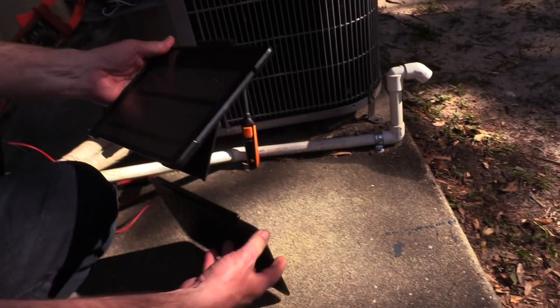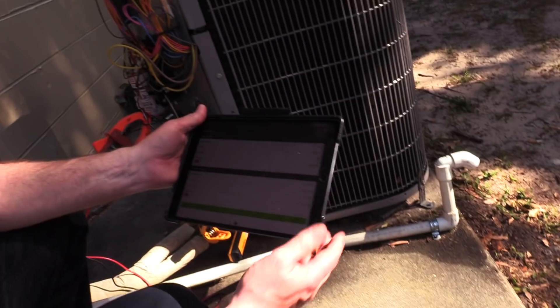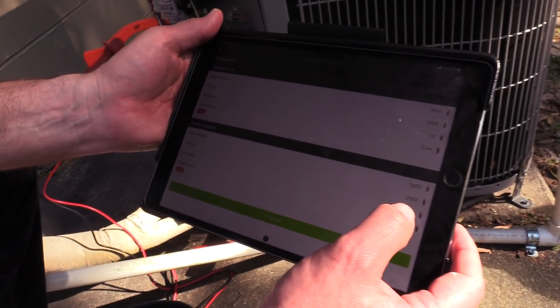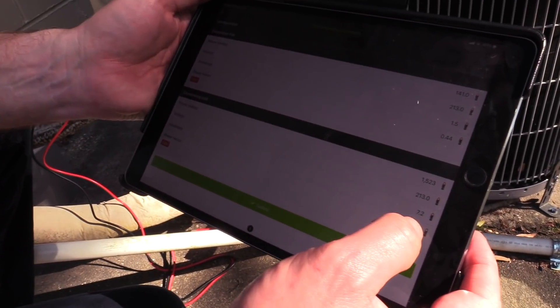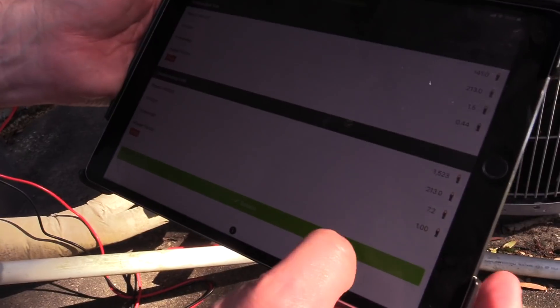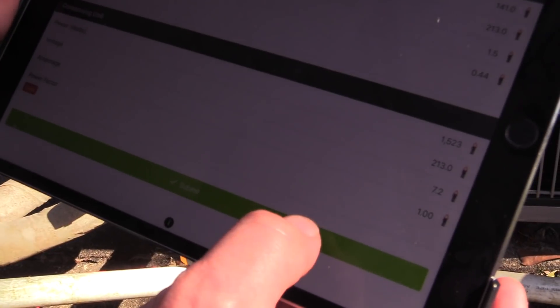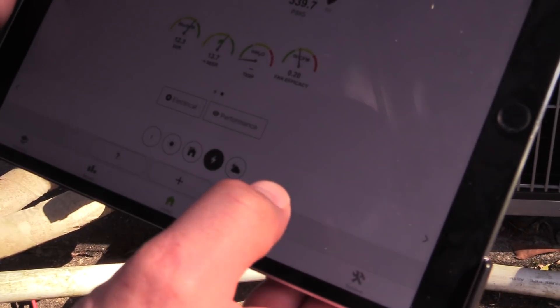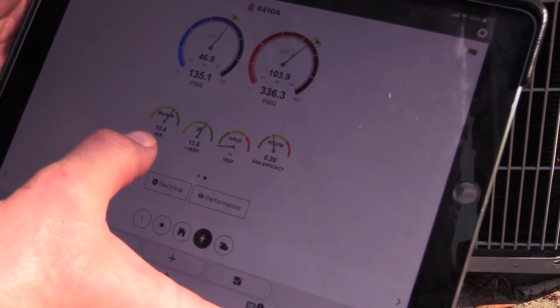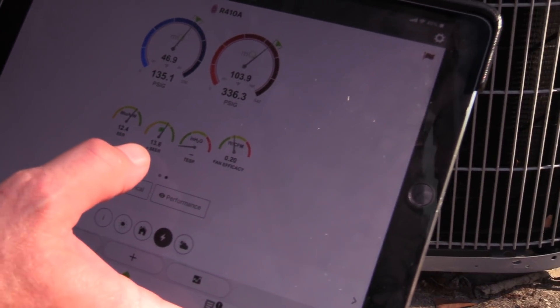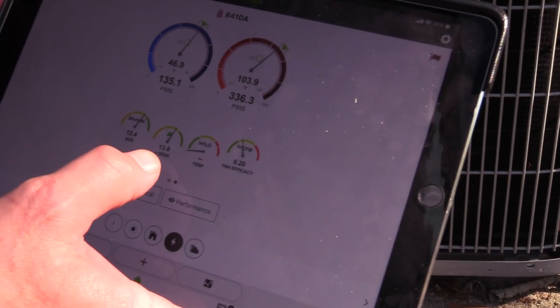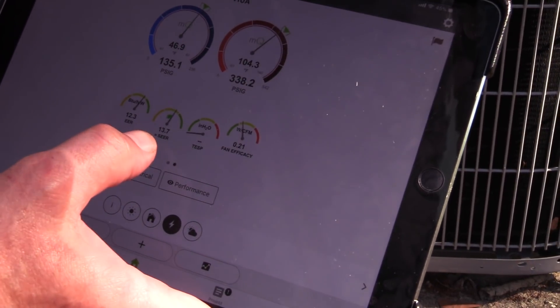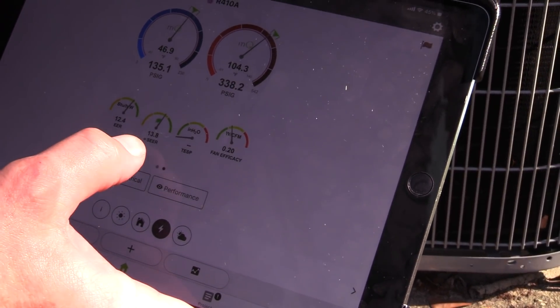All right, so what we got here is about 1500 watts, 213 volts, 7.2 amps. We're going to hit submit on this, and now you can see we're running 12.4 EER and about 13.8 SEER. We're right on spot, and you can expect a 13 SEER unit to run over 13 SEER when we're outside of design conditions.